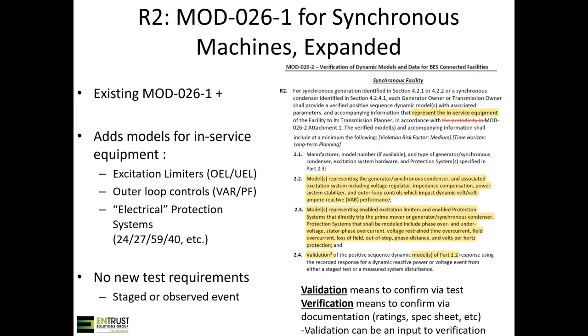We're not asking anyone to go out and actually run into their loss of excitation relay, that would be a very bad day for everyone. So really that's office work, converting the settings in a relay or limiter into the model representation. With Kestrel, even to satisfy our own curiosity, we've had great success testing and validating excitation limiters, but that's because we feel it's best practice. At this point, that's not a proposed requirement for Mod 26-2.